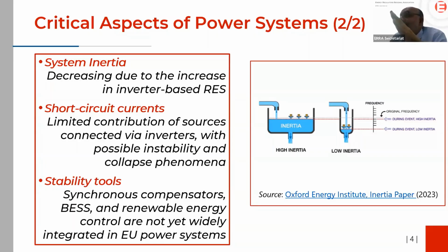But how fast does the level change? It changes faster if the pool is smaller, if it has less inertia. So inertia is very important because when something occurs in frequency, if there is less inertia, it occurs more rapidly, and therefore it's more difficult to mitigate this change in frequency.